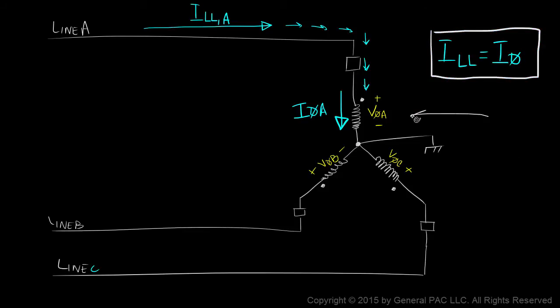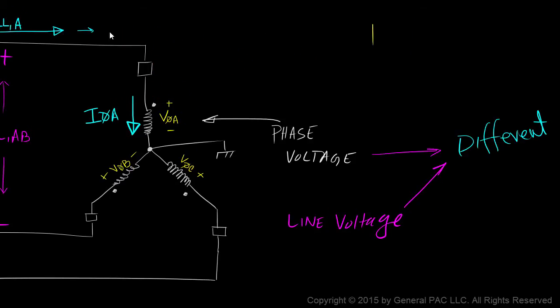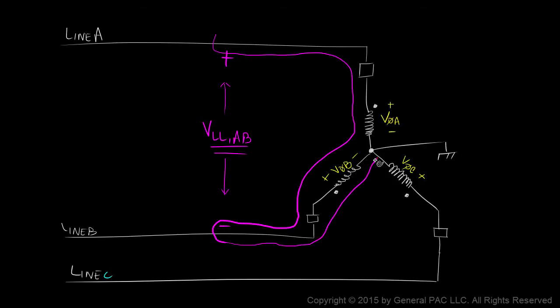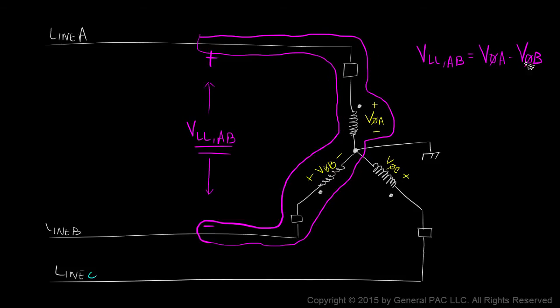We understand that phase voltages are measured across transformer windings while line-to-line voltages are measured across two different lines. For a Y-connected transformer, we can expect the line-to-line voltage to be different than the phase voltage. It's very clear from this illustration that the line-to-line voltage across line A and line B encompasses phase A winding and phase B winding. From our last module, we understood that the line-to-line voltage across line A and line B is equal to phase A voltage minus phase B voltage.